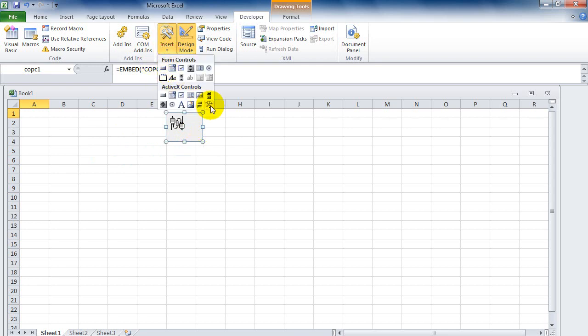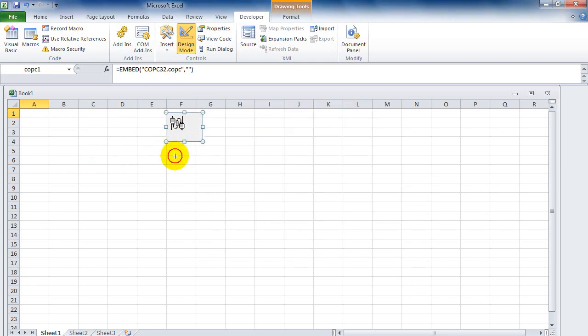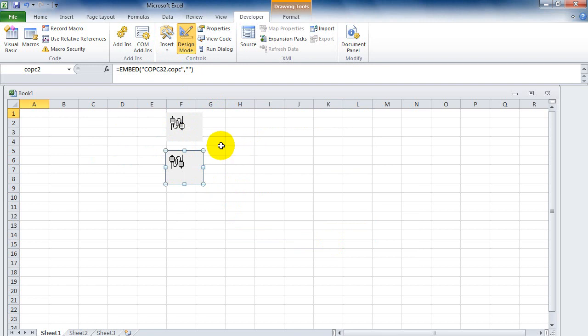You can place another control on the sheet. Each control can connect to OPC tags, with a maximum of 60 tags per control. So if you need to connect to more than 60 tags, you need to add another control.